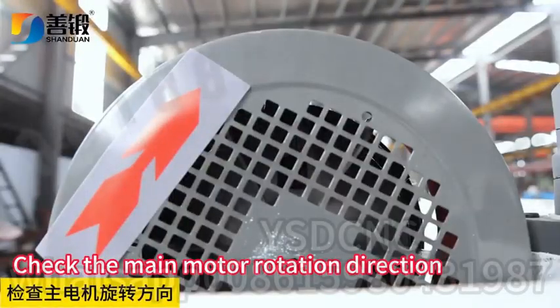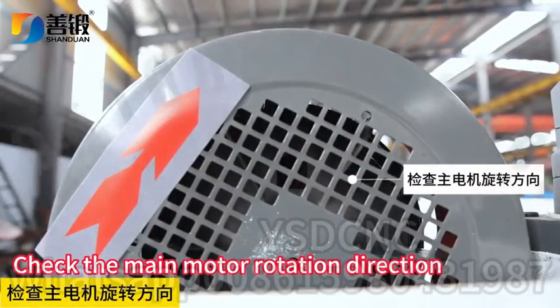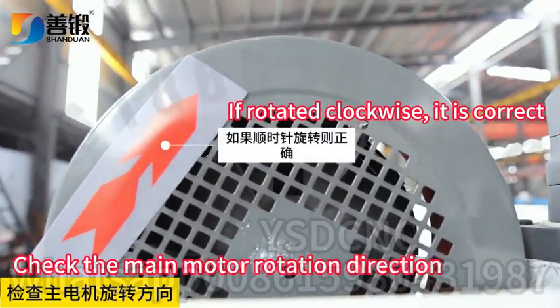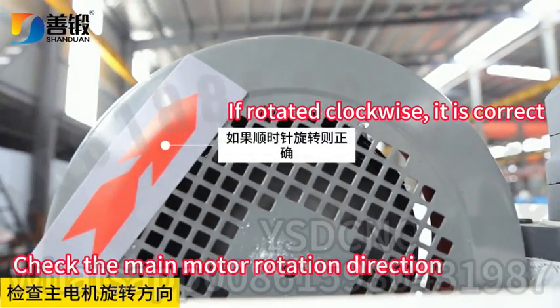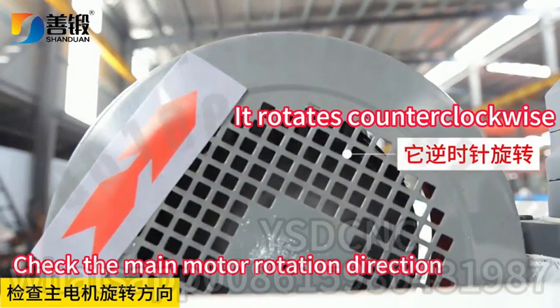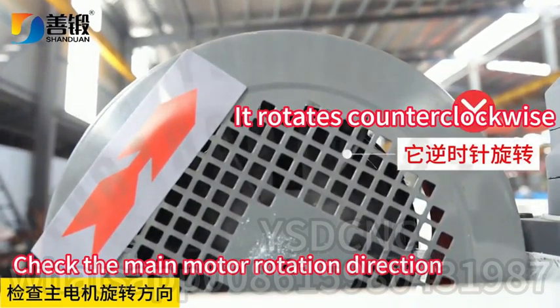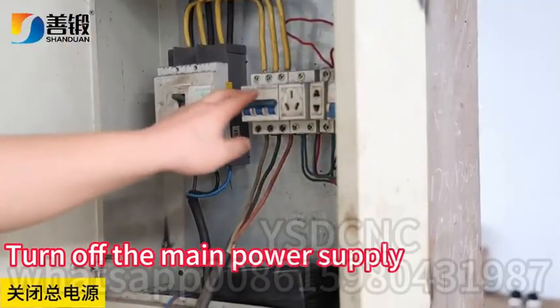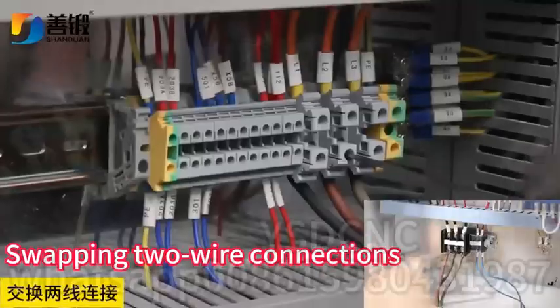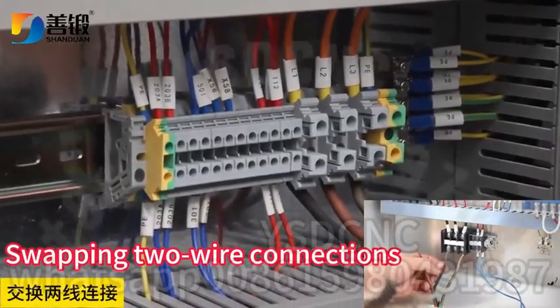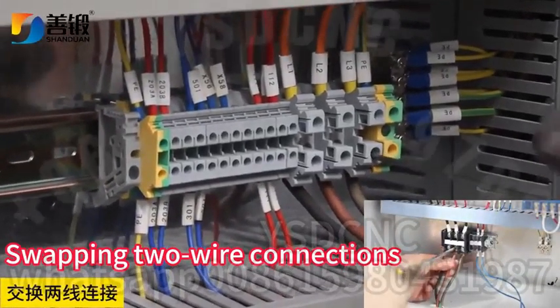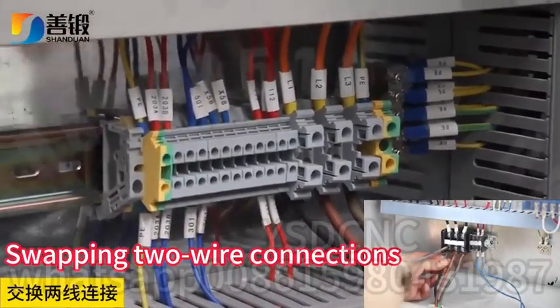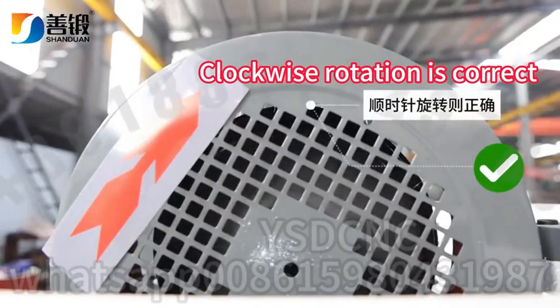Check the main motor rotation direction. If rotated clockwise, it is correct. If it rotates counterclockwise, turn off the main power supply. Swapping 2 wire connections. Clockwise rotation is correct.